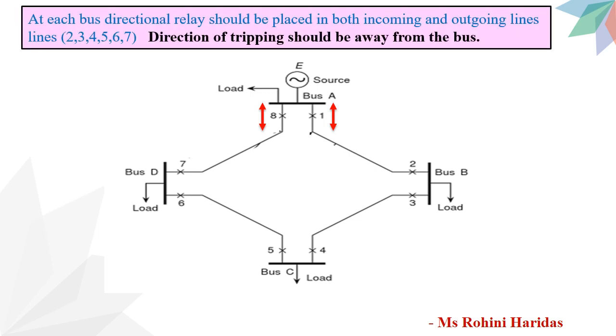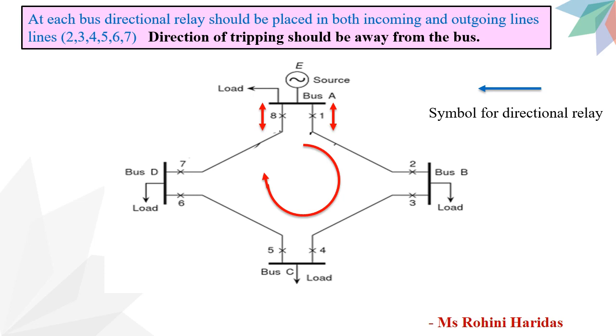Rule number 2: at each bus, the directional relay or reverse power relay should be placed on both incoming and outgoing lines, and the direction of tripping should be away from the bus. This is the symbol for the directional relay. Assuming we go in the clockwise direction: at bus B, relay 2 is incoming and relay 3 is outgoing — both should have directional relays. At bus C, relay 4 is incoming and relay 5 is outgoing. At bus D, relay 6 is incoming and relay 7 is outgoing.